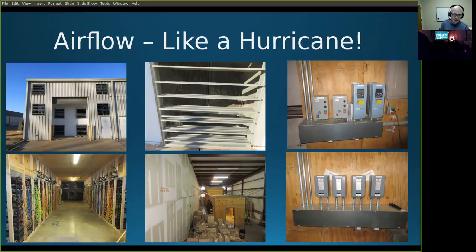And then the bottom left, that's we kind of created an air tunnel. So I'd say that's maybe 1,000 square foot, times 10, maybe 10,000 cubic foot little room that we created, kind of a plenum, and we jam a bunch of air in there, and then we have the miners just take a suction on the cold air that's jammed into there, and they blow it out into the outer room. That's the plan that worked for us on this.